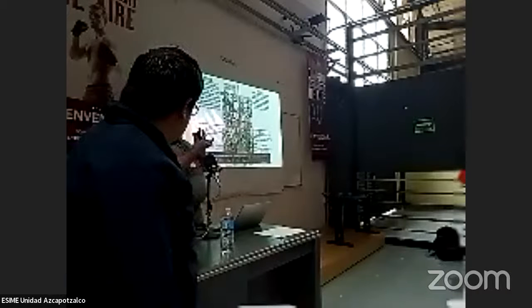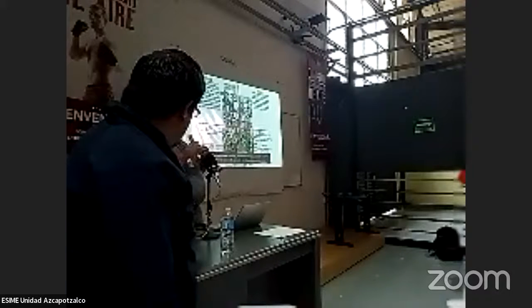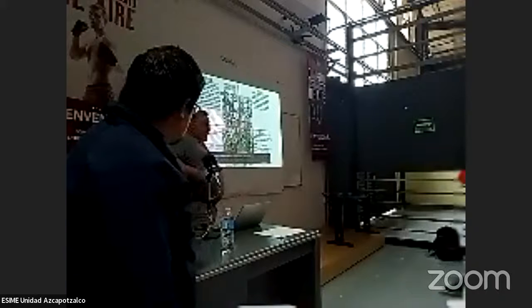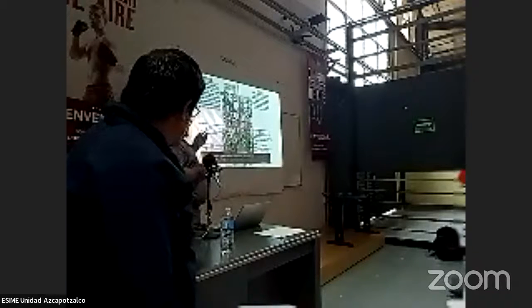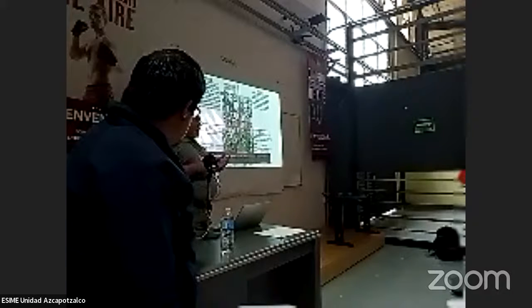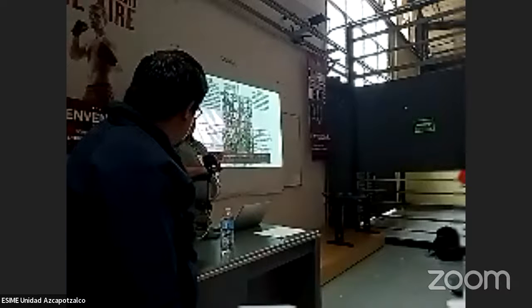There are also times when the compressor is just locked up and it won't move. Check, right? David was talking about checking amperage on all legs. If that motor is locked up, there's going to be a higher amperage because it's trying, but it's not turning. So there are several ways you can determine whether it is the board or the compressor. Typically, what I tell people when they are troubleshooting boards is: power in, power out. Power into the board and power out of the board. If both are good, it's something else, so look for something else.